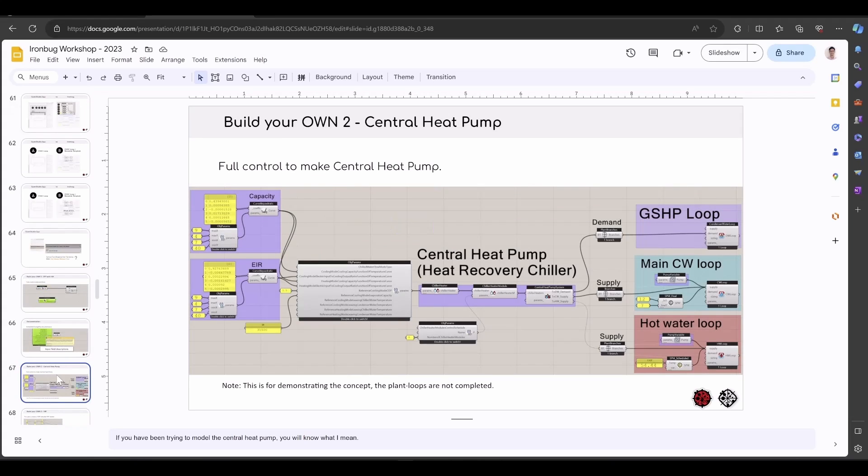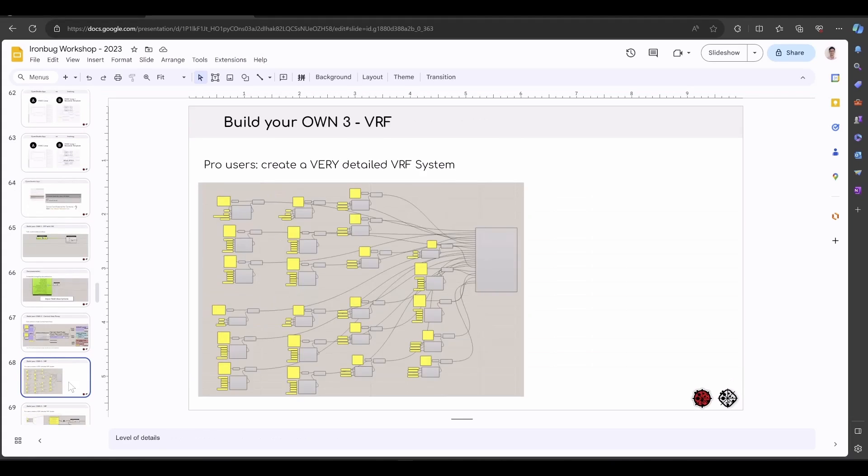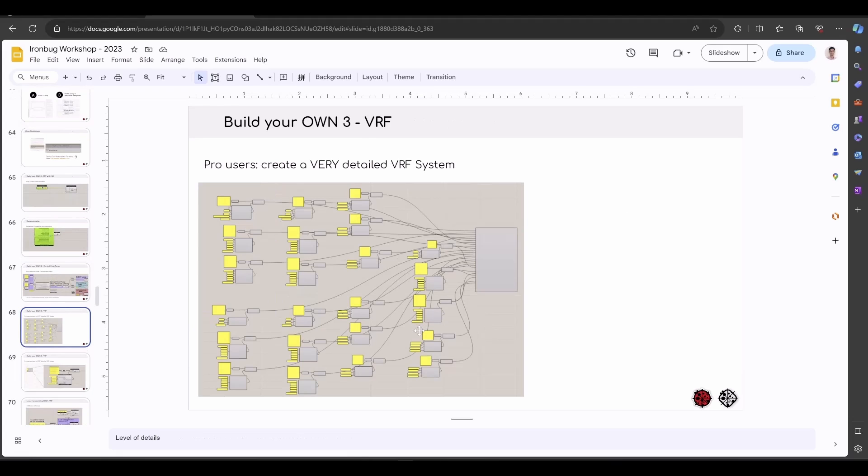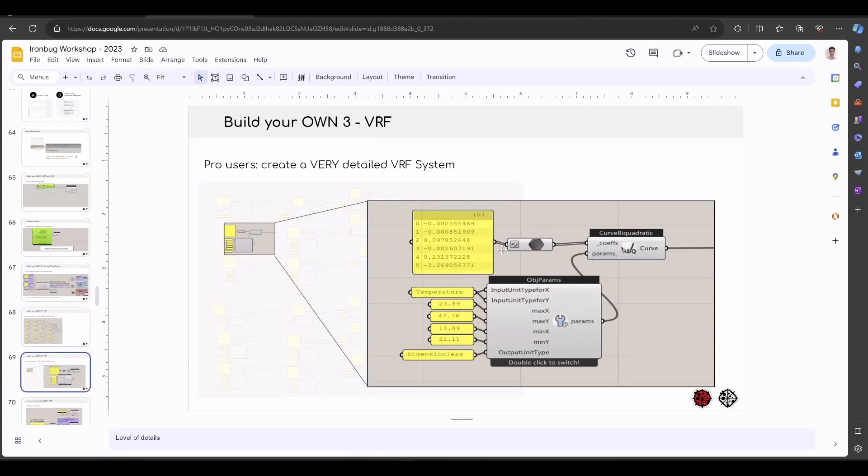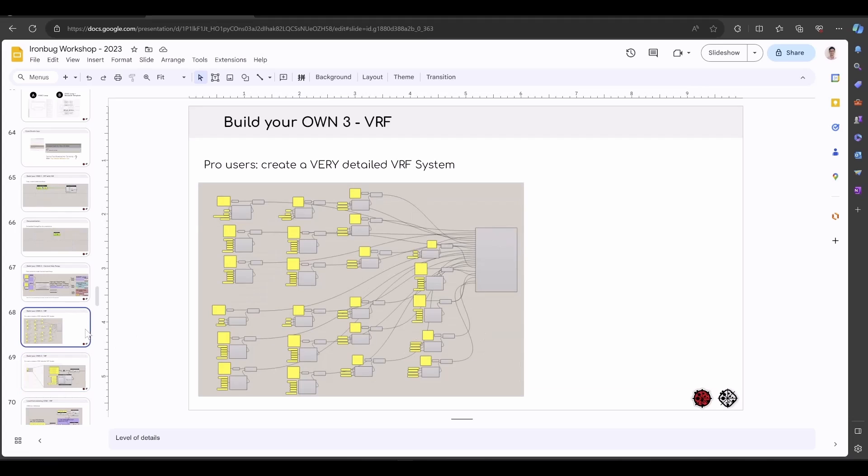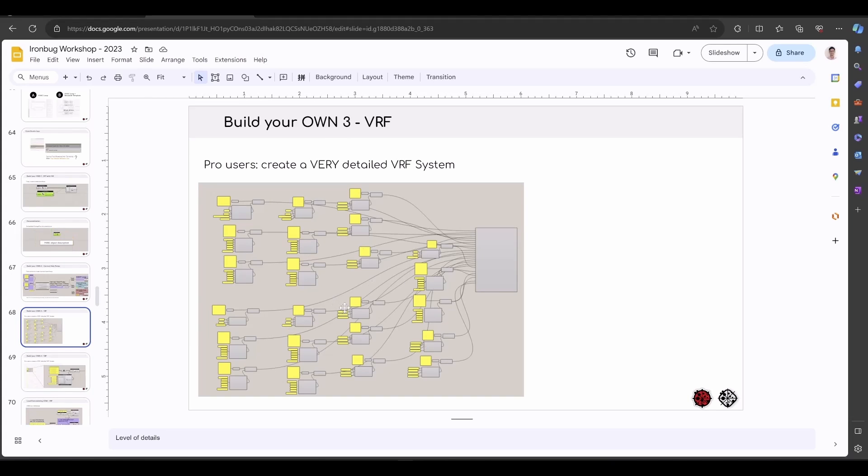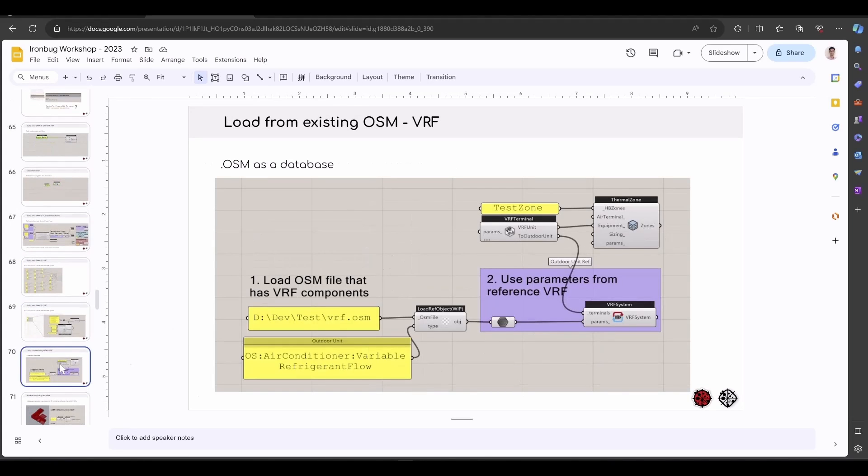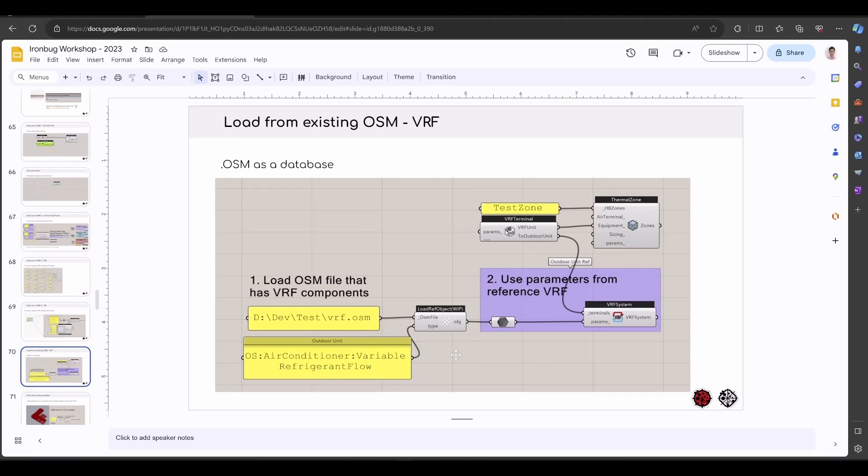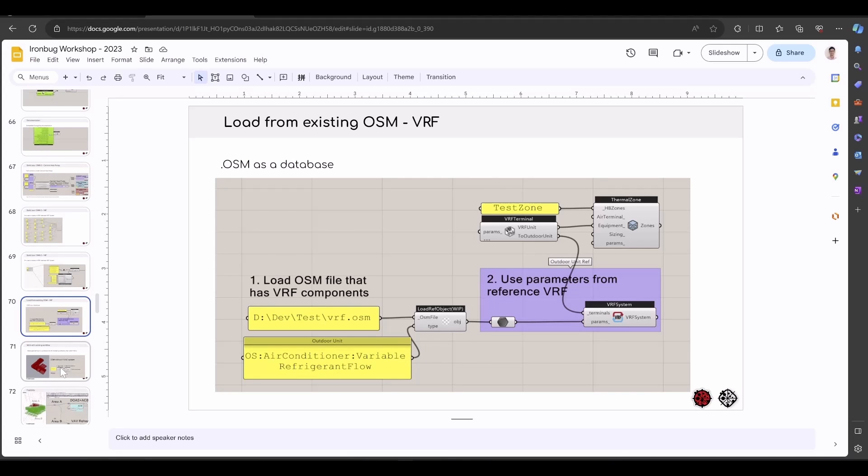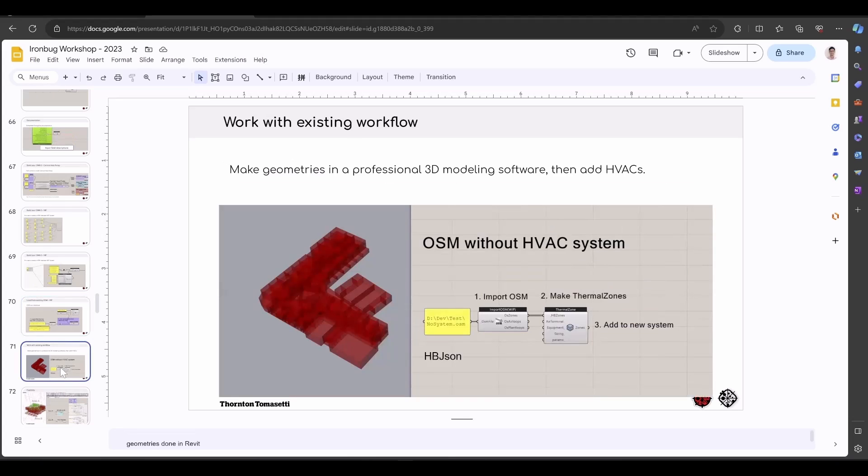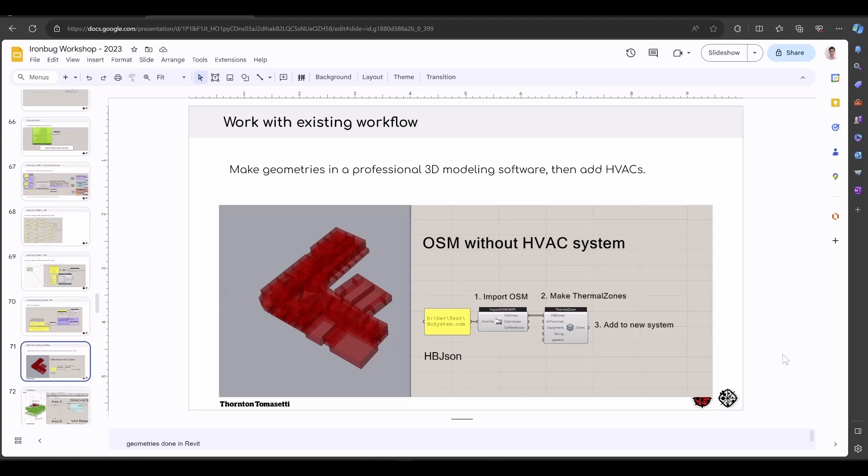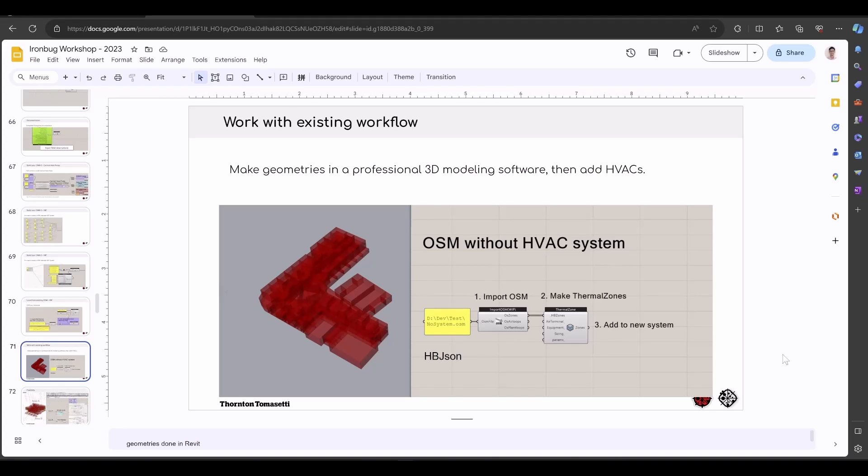You can have full control to make a central heat pump system. And of course, you can set up a very detailed VRF system with all curves. Once you set up in one project, you can reuse it very easily by copying these performance curves into another project. If you have an OpenStudio OSM that contains a VRF system inside, you can just import the VRF system and reference that system in your new model. Even though I think the Rhino platform is the best geometry modeling platform, you have the freedom to use whatever your existing workflow is to build the geometry first and import the model inside Grasshopper and assign the systems here.